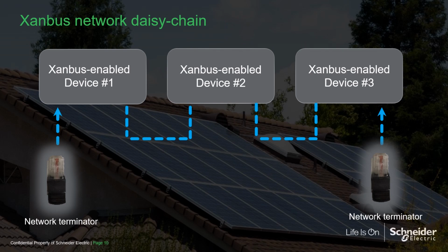Daisy chain is the preferred method for connecting Xanbus devices. A multi-drop backbone is not recommended. Every Xanbus device has 2 Xanbus ports to daisy chain together any number of devices. The only exception is InsightHome, which has a single Xanbus port internally terminated at 120 ohms.